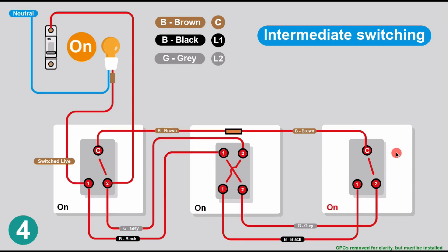We walk to the third switch and switch it on, so all switches are now on. Following the power: it comes in through the common, through the second two-way switch, through the intermediate, and yes - the switch is on, the light is on. Going the other way on the grey, that's not making a connection - but the light is on.